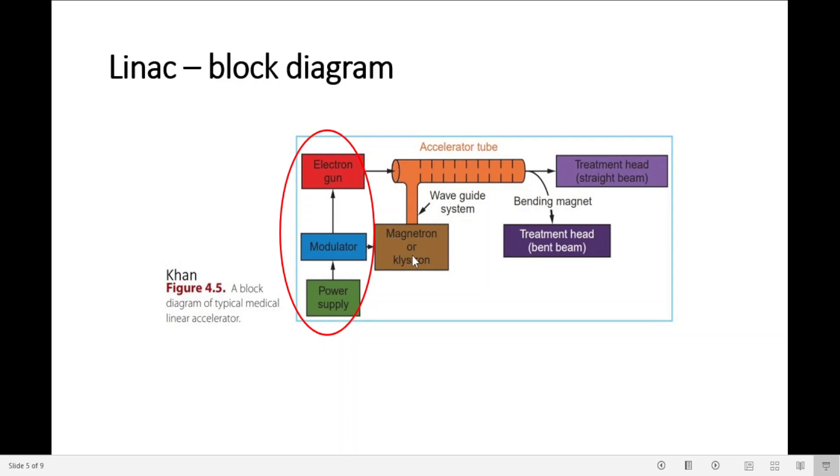The high power oscillator system depends on the LINAC design. The system will either have a magnetron or a klystron. It will not have both. It's either or. The magnetron is a microwave generator. It is, by itself, a high power oscillator.